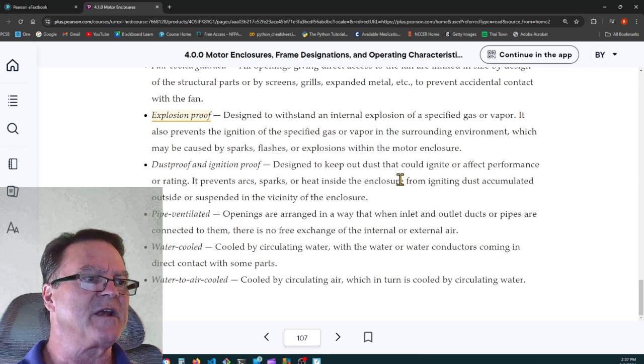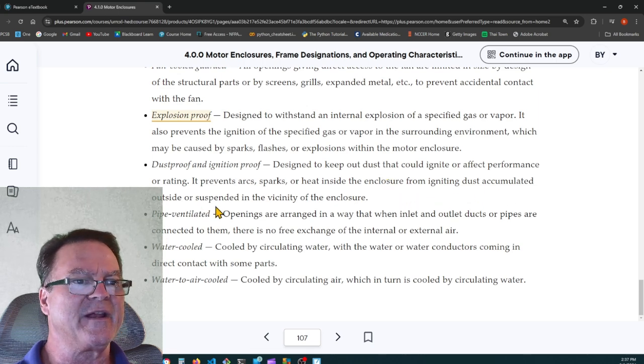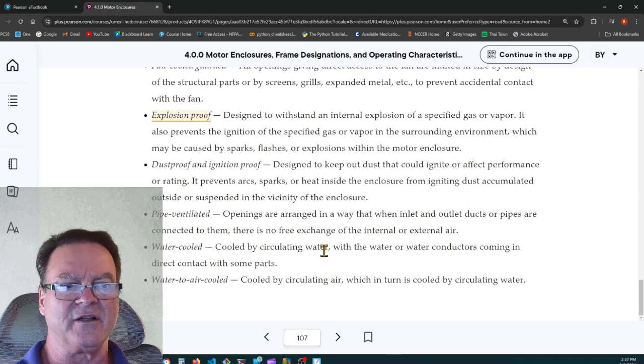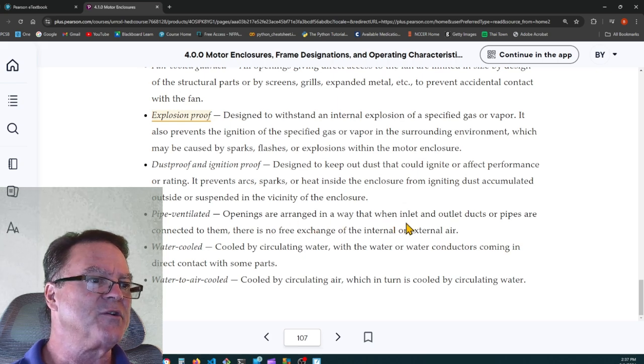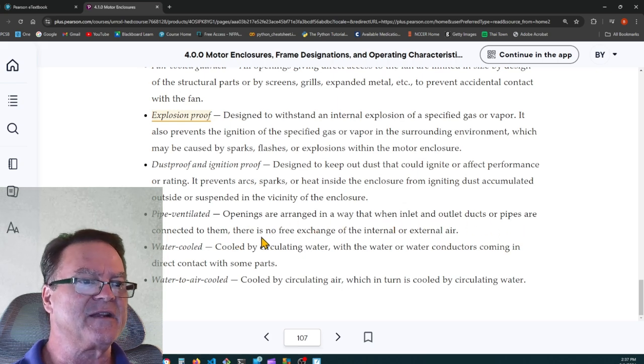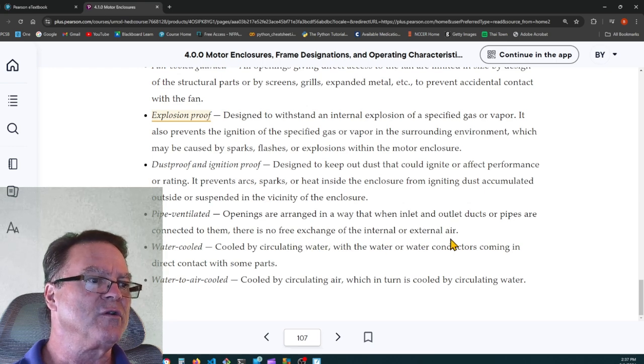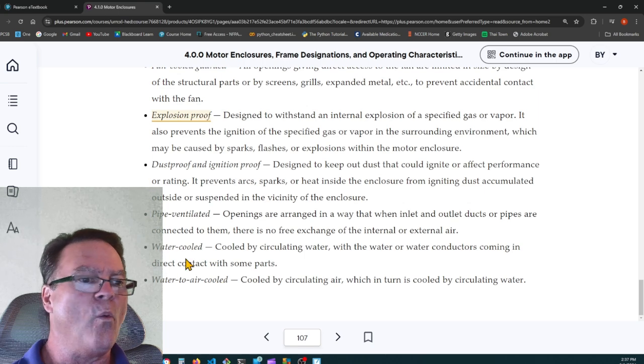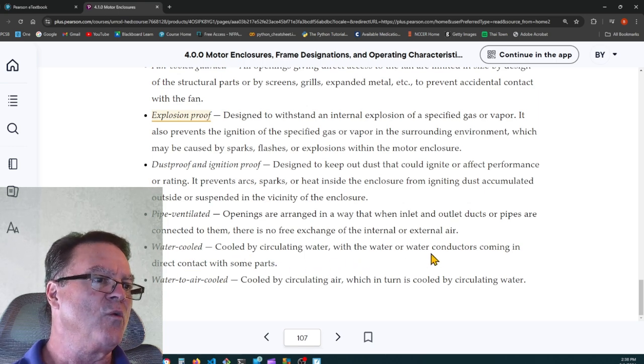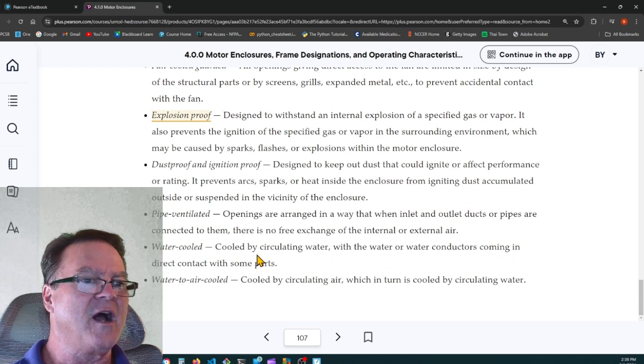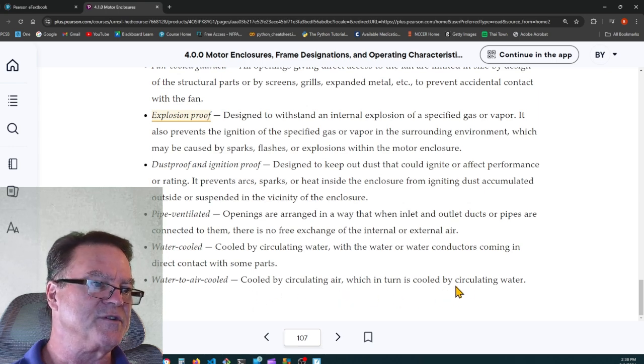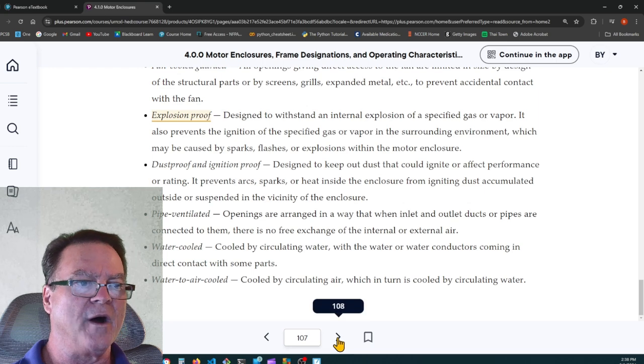Dust proof and ignition proof, designed to keep out dust that could ignite or affect performance or rating. It prevents arcs, sparks, or heat inside the enclosure from igniting dust accumulated outside or suspended in the vicinity of the enclosure. Pipe ventilated actually has a pipe that goes outside of the room. Openings are arranged in a way that when inlet and outlet ducts or pipes are connected to them, there's no free exchange of the internal or external air. Water cooled, cooled by circulating water with the water or water conductors coming in direct contact with some parts. And water to air cooled, it's cooled by circulating air, which in turn is cooled by the circulating water.